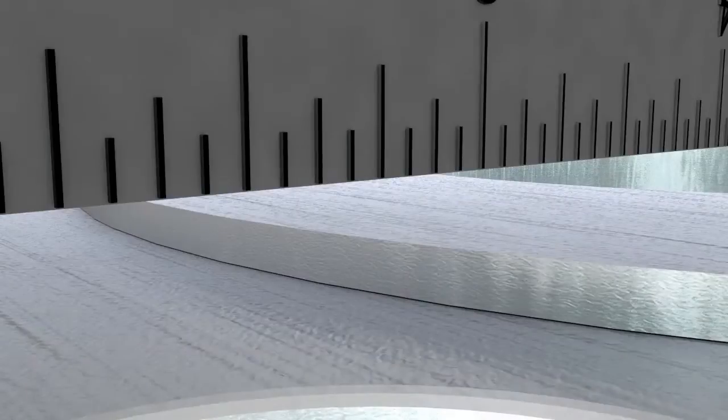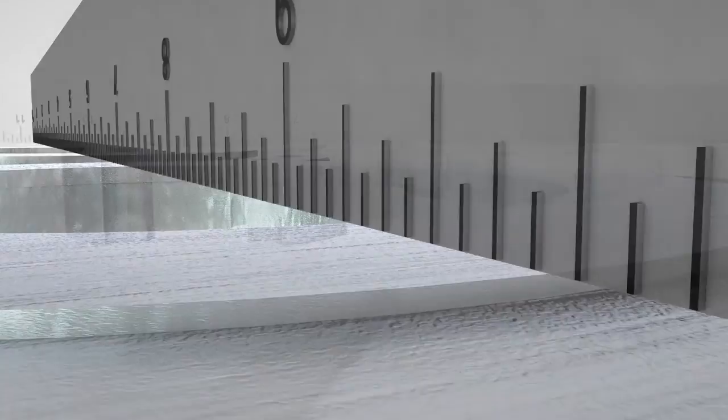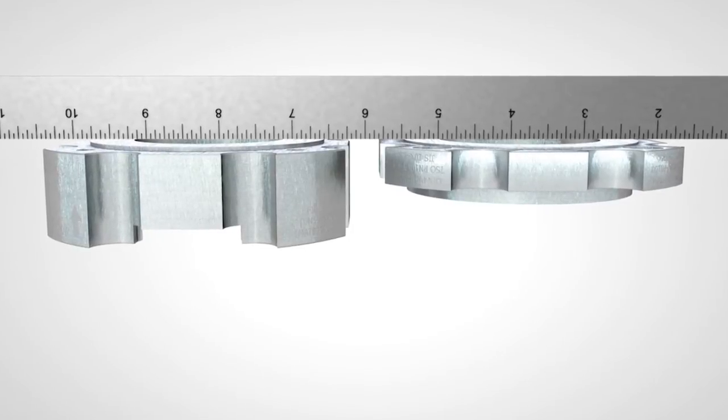To verify that the holder has not become deformed, place a straight edge on the flat flange mating surfaces of the base and hold down. If the surfaces are not parallel with the straight edge, the holder should be replaced immediately.